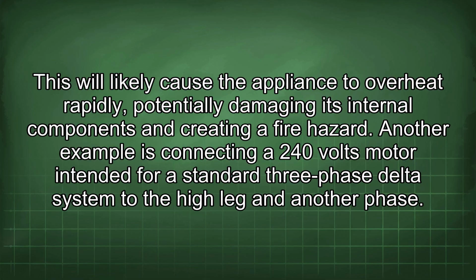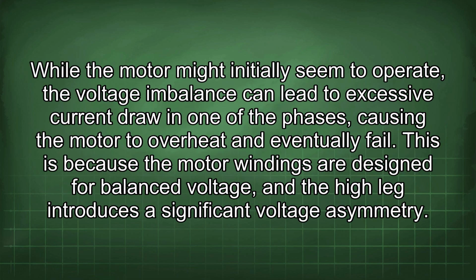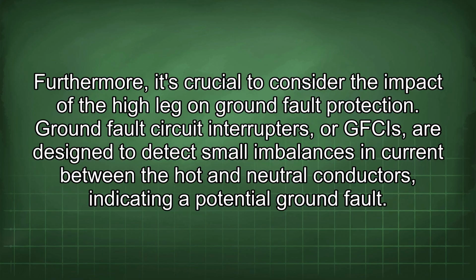Another example is connecting a 240 volts motor intended for a standard three-phase delta system to the high leg and another phase. While the motor might initially seem to operate, the voltage imbalance can lead to excessive current draw in one of the phases, causing the motor to overheat and eventually fail. This is because the motor windings are designed for balanced voltage, and the high leg introduces a significant voltage asymmetry. Furthermore, it's crucial to consider the impact of the high leg on ground fault protection.